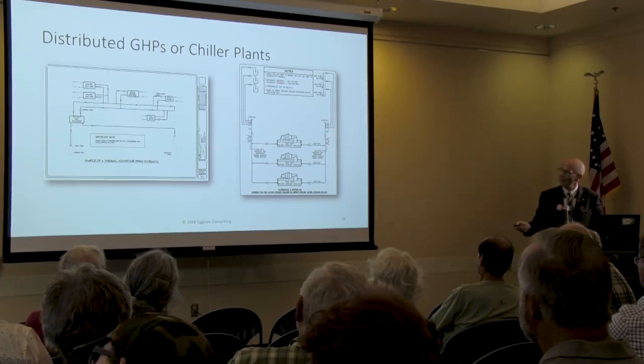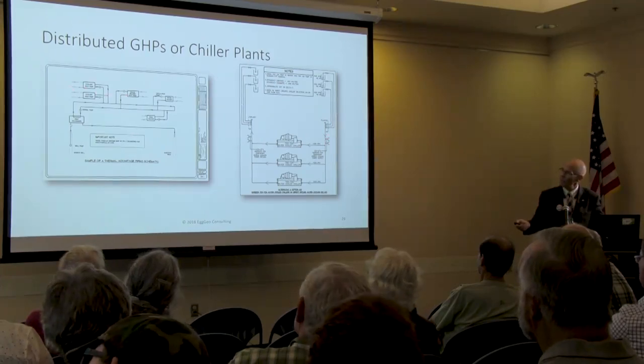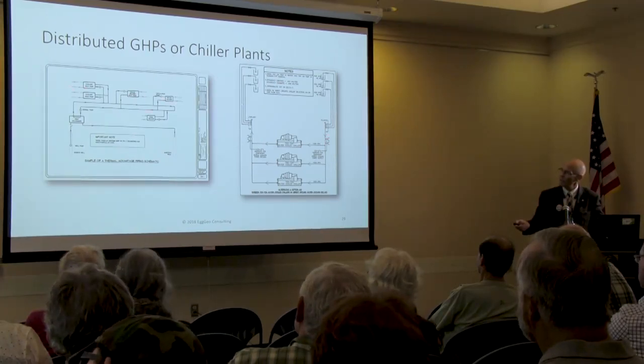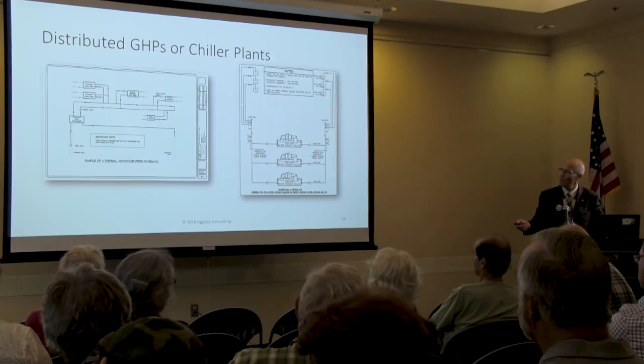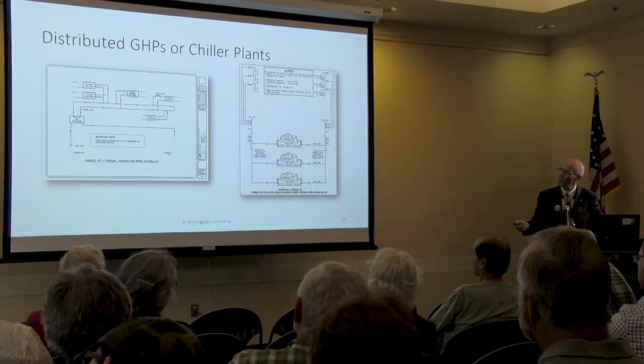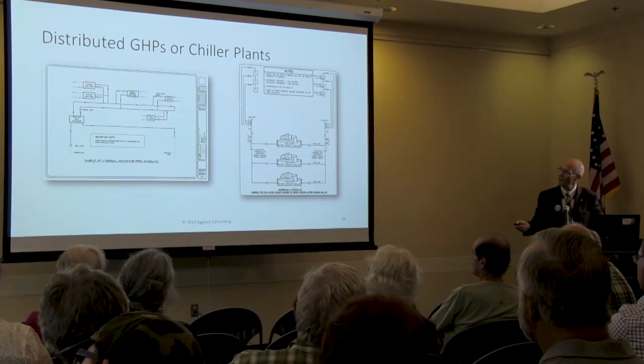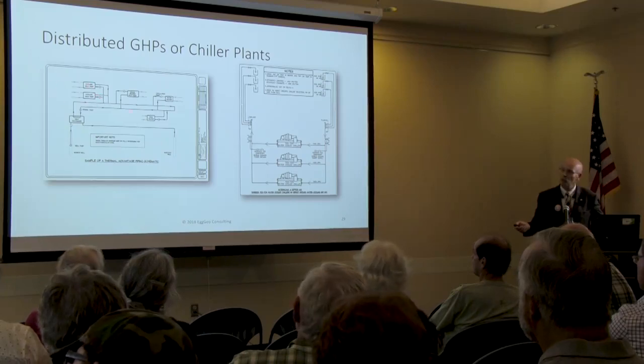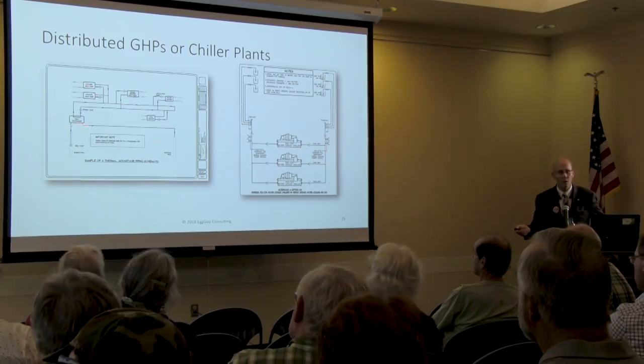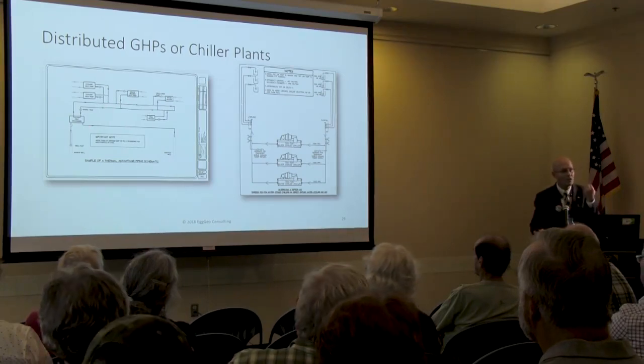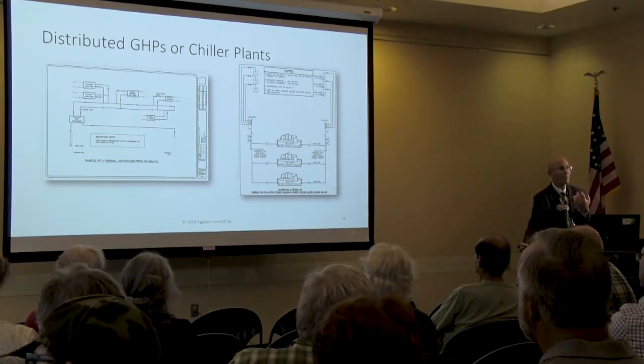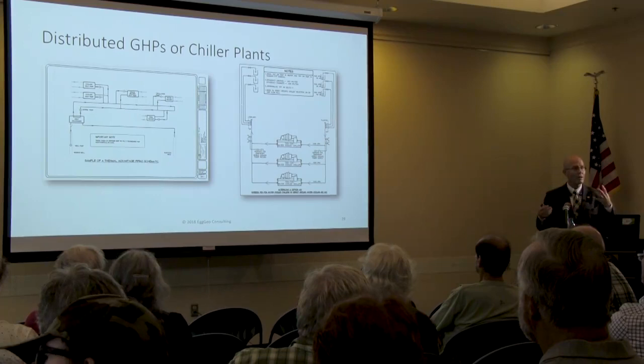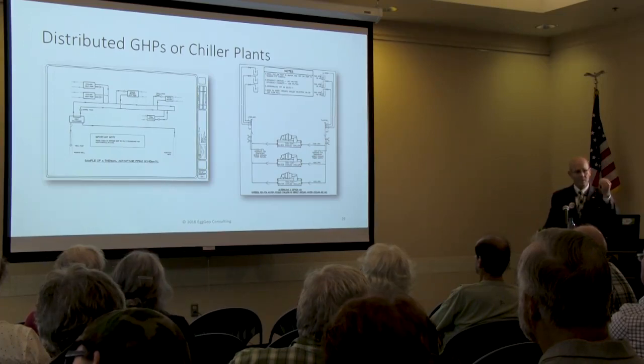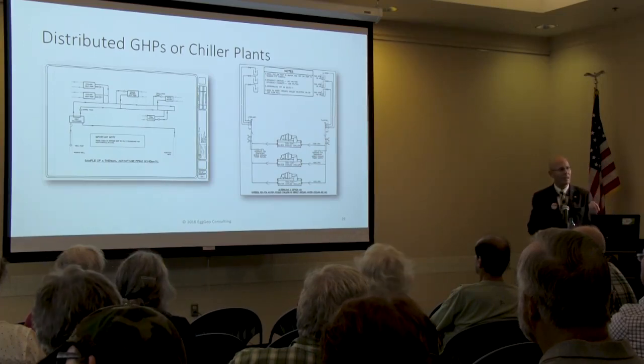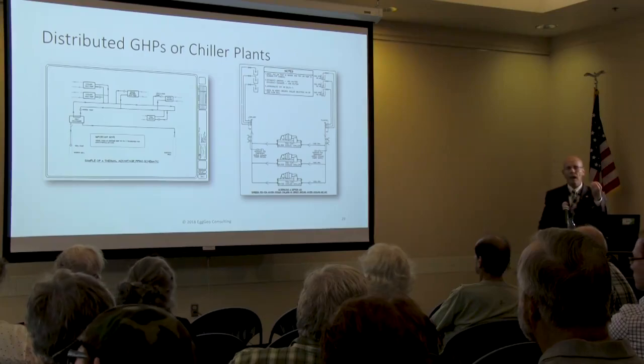Or you can have a bunch of individual heat pumps that are doing different and various heating and cooling loads. And much like the polar bear and elephant exhibit, some of the heat pumps are doing heating, some of them are doing cooling, so some of them are pulling energy from the condenser water loop, and some of them are rejecting energy. So there, what happens is, remember this term, thermal advantage load sharing.